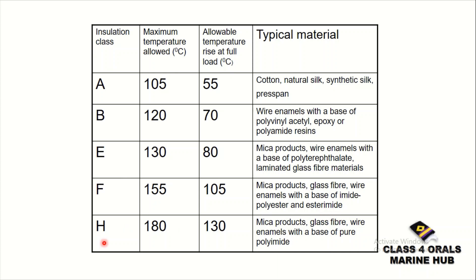Last is Class H insulation. It has a maximum allowed temperature of 180 degrees centigrade. With full load, the allowable temperature rise is 130 degrees centigrade. The typical materials are mica products, glass fiber, and wire enamels with a base of pure polyimide.